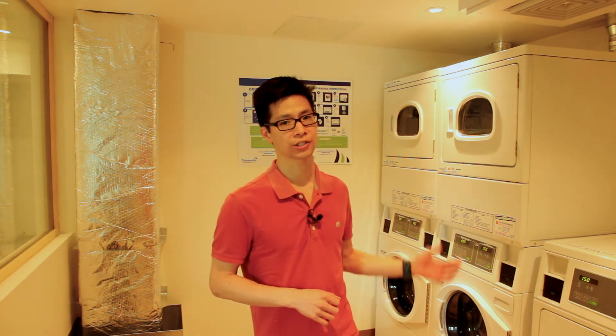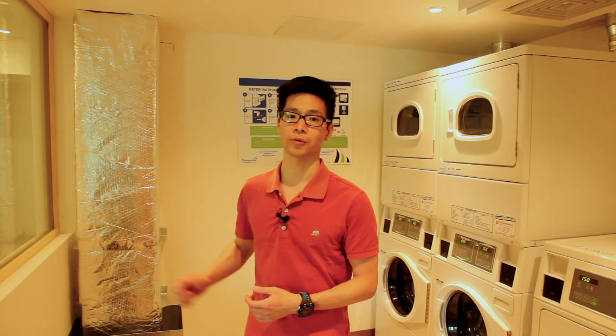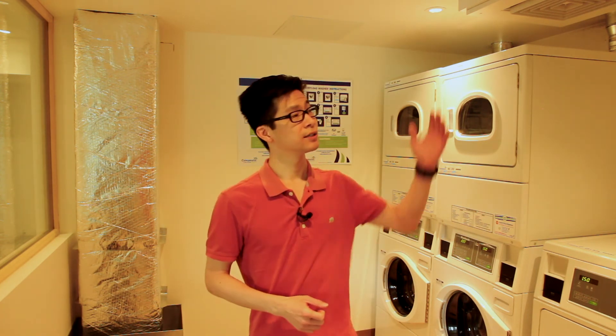Inside the laundry room, we have coin-operated washers and dryers. Common practice is to have ductless dryers; however, since a coin-operated ductless heat pump condensing dryer is not readily available, these dryers vent to the outside. In lieu, makeup passive air is provided through this duct on a motorized damper. Since the air is coming straight from the outside, space heaters are used to keep this space warm.